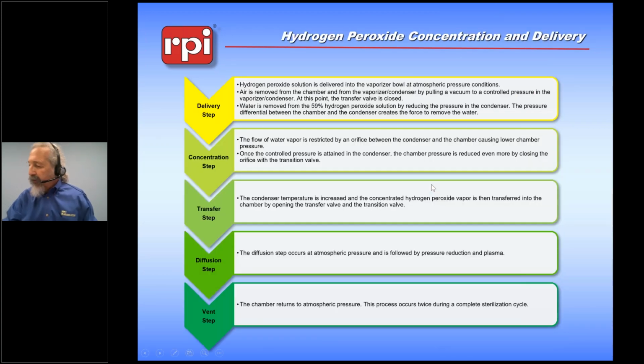Okay, hydrogen peroxide concentration delivery process. So we need to be able to get the concentration of the peroxide down to a usable amount. So what we're going to do is put it into a heated chamber, and that heated chamber is going to convert the entire amount of the peroxide and any water that it carries with it into a vapor. Once we can get that vapor onto our condensing coil, we'll take the hydrogen peroxide out, and then we will take the water, separate it, get rid of the water, and continue to concentrate down the hydrogen peroxide.